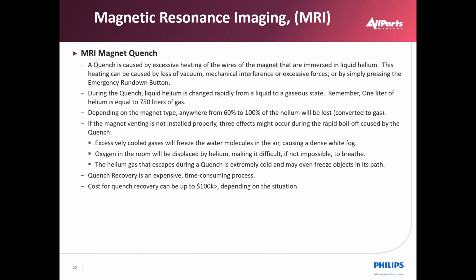I'm sure that at least some of you have heard of an MRI magnet quench. A magnet quench is caused when excessive heat is applied to the coils in the magnet vessel. A magnet can quench from a variety of factors, but in case of emergency, it can be quenched by pressing the system's emergency rundown button. Remember the helium conversion from 1 liter of liquid to 750 liters of gas. This causes excessive internal pressure of the magnet vessel.